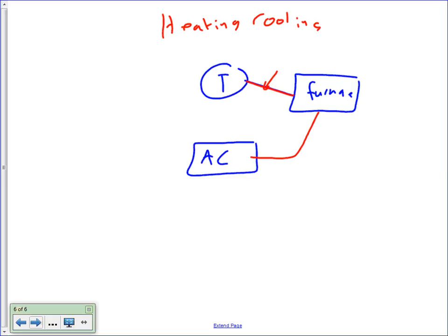Phone data riser, one line diagram, trench. No, security, I use phone data, we didn't do that one. Let's use 16 just because of that. So that would be number 16, 4, thermostat cable, not twisted. And also this one, let's just say they're using 16, 4. Thermostat cable. They're not twisted, my understanding. I don't think they twist these. So you're taking a class 2 circuit, guys. 16-4, 4 conductors.